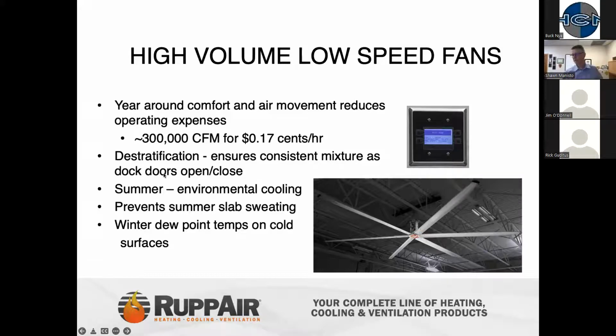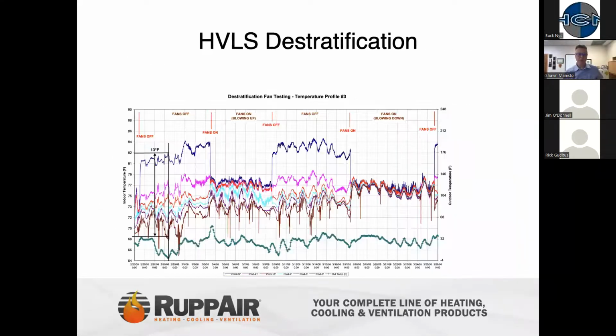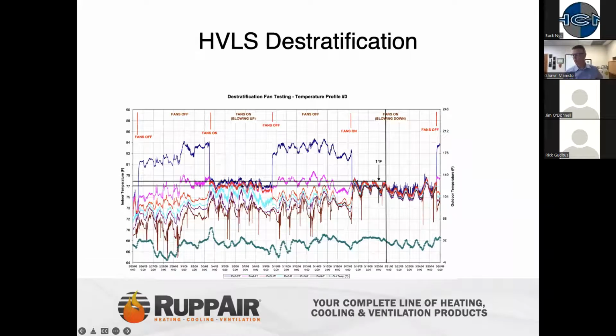Great for destratification in the wintertime, but also great for summertime cooling, having some of that sensible cooling across your body. Prevents basically summer slab sweating, but also helps prevent winter dew point on those cold surfaces. This is a picture showing, in these high areas here, the stratification within a space with the HVLS fans off. And if we go to the next slide here, it pins down where we were running in much more balanced temperature ranges, a 1 degree temperature range with the HVLS fans on when we're in a heating mode application.